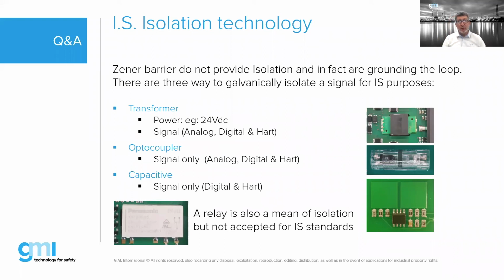They provide means of isolation. The difference on a transformer is you can also transfer power, 24 volt. The other means can only transfer a signal, analog or digital, so very, very low voltage. For example, an optocoupler is basically 2 LEDs flashing to each other, and they transfer only light. So you cannot transfer 24 volt. They have to be specifically designed and specifically certified to do the job. They're not standard components. It's not a normal transformer. It's not a normal isolator. There are a lot of rules to make it intrinsically safe, so-called infallible components. But now, the question was also about a relay. A relay is a means of isolation, and a relay provides isolation. You might use relays for up to 2.5 kilovolt of isolation, but a relay cannot be used as a means of isolation for IS purposes.